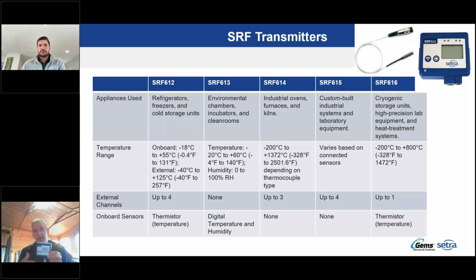There's a little breakout module that you can attach to 4 probes, and you can individually configure all 4 of them. So one could be in a -20 freezer, one could be in a standard fridge, and one could be in an incubator, all next door to each other, all with independent alarm limits and independent alarm delays.